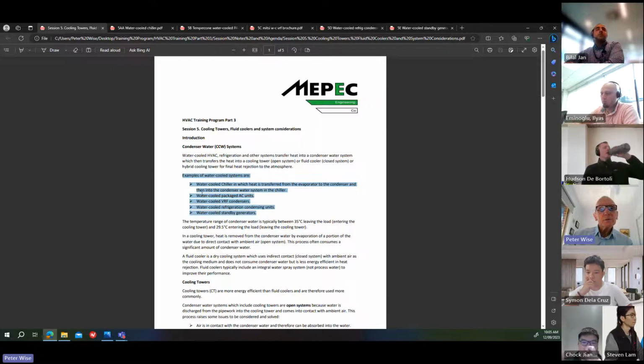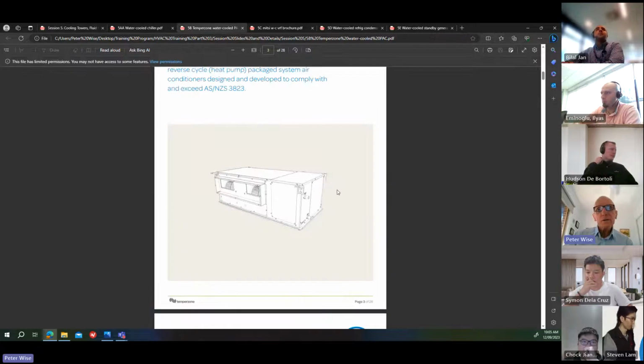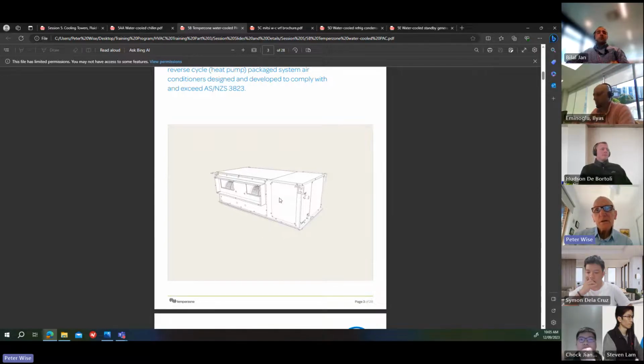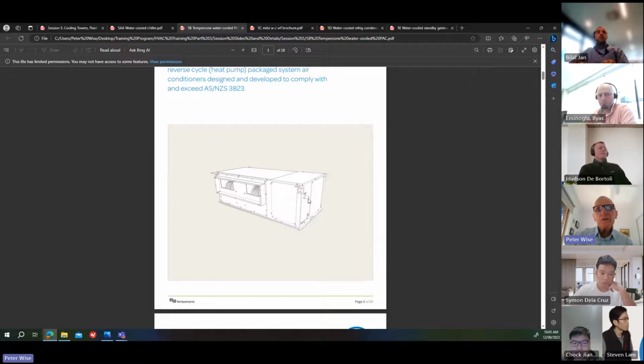So there's the water-cooled chiller, and there might be water-cooled packaged air conditioning units. I've got a picture of one here, which is a Temperzone unit. This is a packaged unit which has got a compressor and a condenser coil in it. And this can be installed above a ceiling or in an adjacent room, usually fairly close to the occupied space. It shows a couple of stubs here, which are the condenser water connections. So they're quite useful. If you've got a cooling tower or a distributed system, you can have one cooling tower which serves 100 units if you want to. You just have to pump the condenser water through the building.